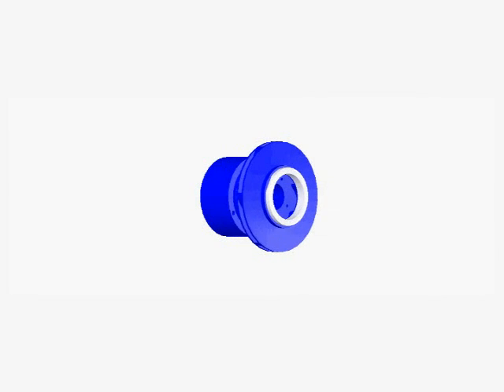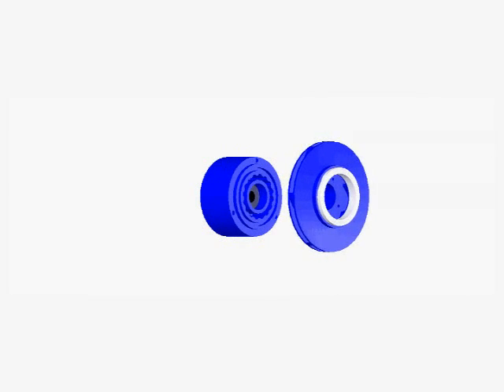The two-piece impeller design allows the impeller or inner drive magnet to be individually replaced. Unfilled polypropylene or PVDF is molded over the inner magnets to eliminate any possibility of fluid contacting the magnets. DB series pumps equipped with carbon bushings are capable of running dry for hours, the longest run dry ability of any mag drive pump in the world.